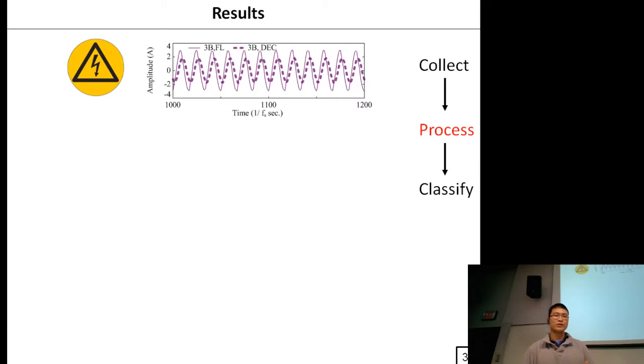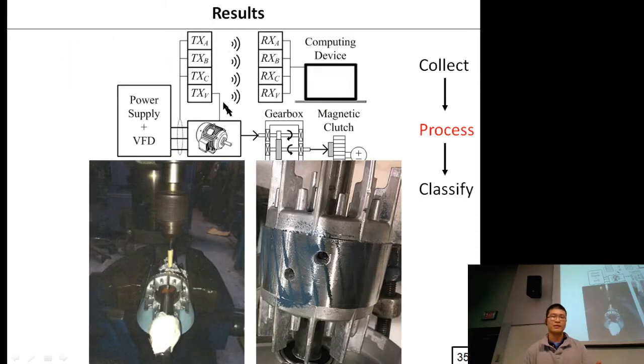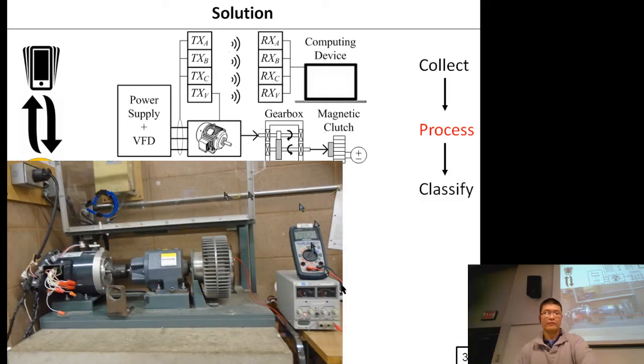And looking into the current, I have this result here, where I have a decoupled motor tested and a fully loaded motor. Decoupled means the shaft is freely running, nothing connected. And then the fully loaded is where I have that clutch current set to the max and make this motor work as hard as it is specified to be able to handle.